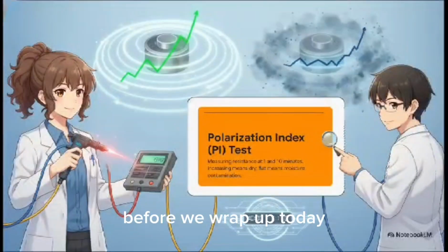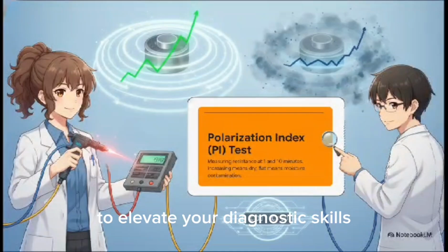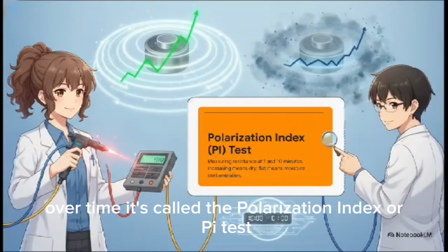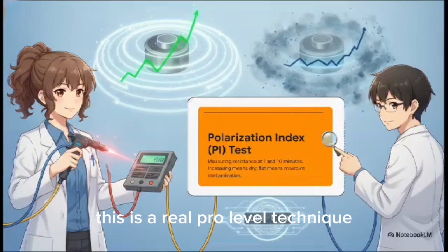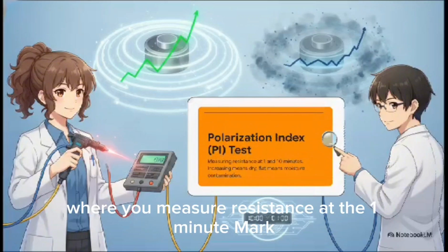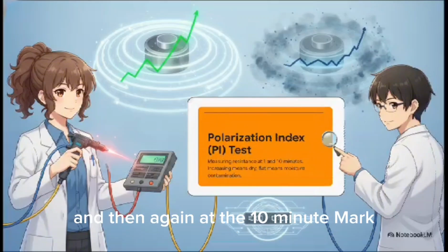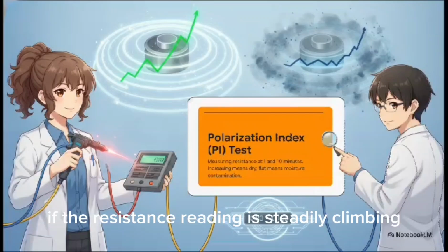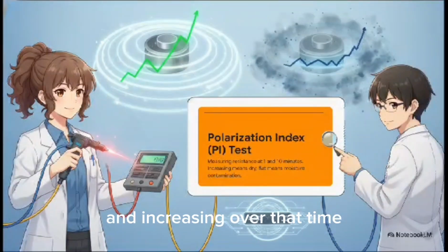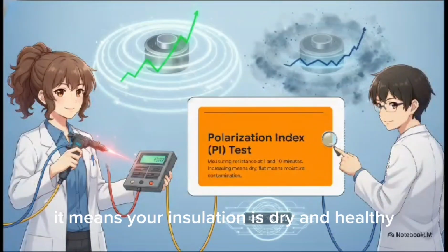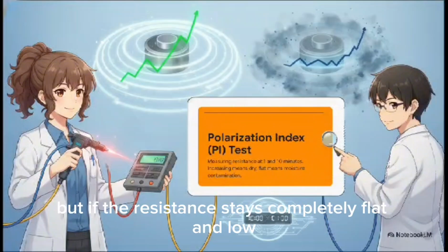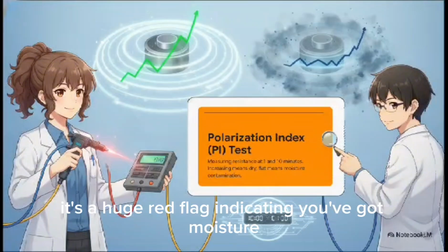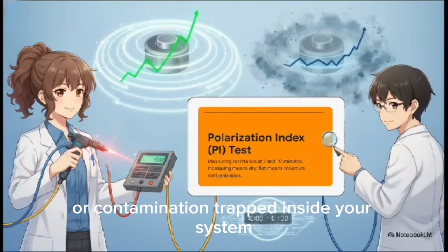Before we wrap up today, I really want to share a quick pro tip to elevate your diagnostic skills over time. It's called the Polarization Index, or PI test. This is a real pro-level technique where you measure resistance at the 1-minute mark and then again at the 10-minute mark. If the resistance reading is steadily climbing and increasing over that time, it means your insulation is dry and healthy. But if the resistance stays completely flat and low across those full 10 minutes, it's a huge red flag indicating you've got moisture or contamination trapped inside your system.